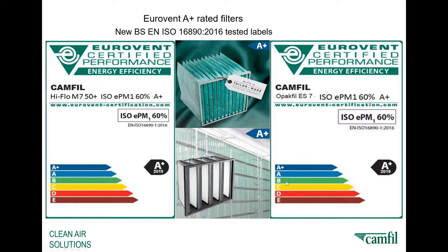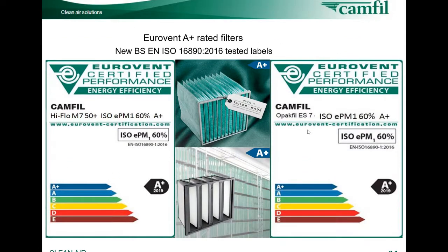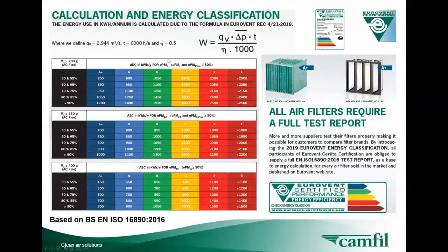You can see the traffic lights here, A+ to E, very efficient down to not very efficient. And this is a good way of having a quick visual aid and seeing how efficient people can get their filters. And this is worked out by this equation as an energy model based on air passing through a filter and the increase in pressure drop over time.